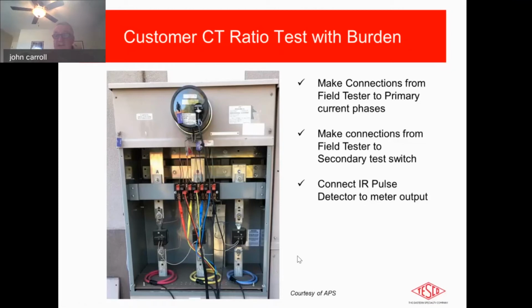This does offer a real good advantage if you have the situation that I mentioned before, where you have a very low load condition. Now it's difficult to take a measurement. If you have a 400 to 5 CT and you've only got 10 amps going through it, that's particularly low. You might be able to read it, but it might take a while. By double wrapping, you now get, instead of 10 amps, you might get 20. So you're pushing the amperage up a little bit, which gives you a better chance of getting the test result. So it's a great feature to have.